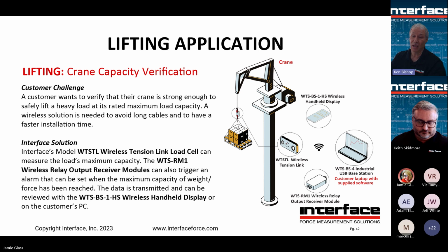So the picture is showing them lifting their test load, which is at the capacity they want to test the crane. They lift it, and as they lift it, of course, it puts a tug onto the tension link, and then the load that the tension link sees is wirelessly transmitted to all three of the devices: the handheld, the BS4 USB base station, which goes to the PC, and the relay module. If a safe load is exceeded, the relay module will click a relay and activate one of the alarms that's set. At the same time, the BS4 is recording the measurement that the tension link recorded into the Log 100 software, and the operator can also be reading a handheld display, seeing what weights are actually being applied to this crane. So very nice, complete system that we can supply, and the customer had success in crane capacity verification.